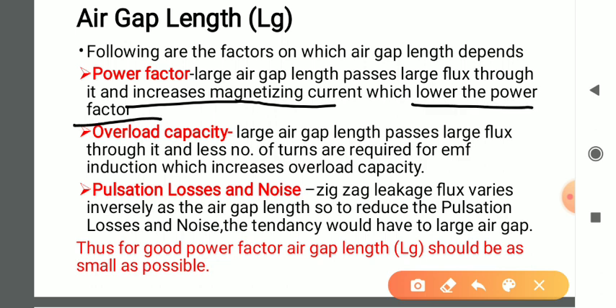So it reduces the power factor — the increased value of the magnetizing current lowers the power factor. So whenever we increase the air gap length we need to compromise with the power factor, and as we know that the power factor directly affects the efficiency, so it means it directly affects the performance of the induction motor.